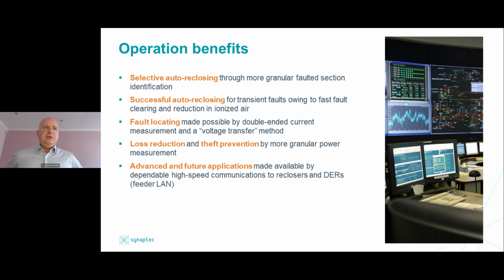Again, speaking about some of the operational benefits, if we can identify the faulted sections, then we can do more sophisticated and more selective autoreclosing or restoration functions. We can locate the faults. If you have voltage measurements at some locations in the network and you have a good knowledge of the impedance between those voltage measurement points and the distributed current measurement points, then you can start to think about sophisticated voltage estimation type functions, which could be used either to detect faults approximately within feeders and to the exact location, and it could also be used to detect potential voltage problems, either excursions from voltage dips or over voltages, for example, if you have a lot of generation connected to a feeder.